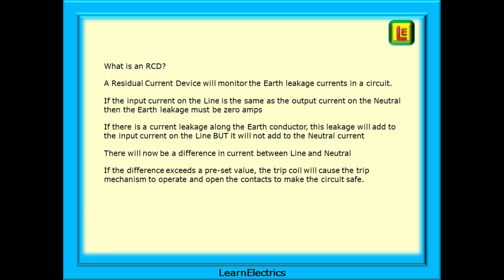An RCD is a residual current device that will monitor the earth leakage currents in a circuit. In simple terms, if the input current on the line is the same as the output current on the neutral, then the earth leakage must be zero amps and the device will not trip. This follows Kirchhoff's laws — what flows into a circuit must exactly flow out; all input currents will mathematically equal all output currents.